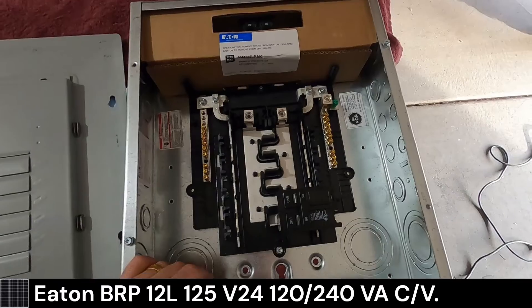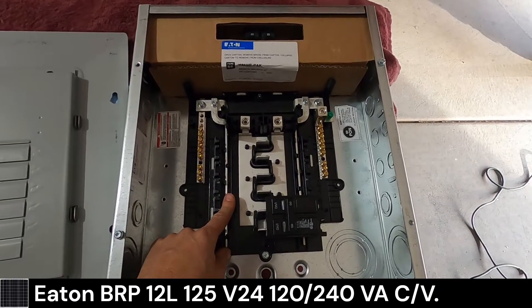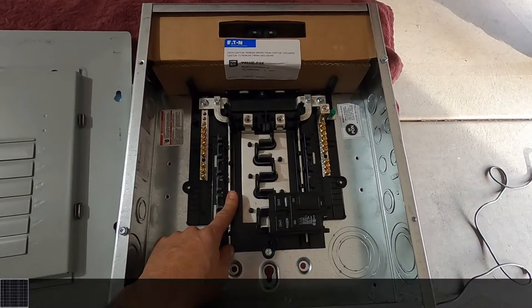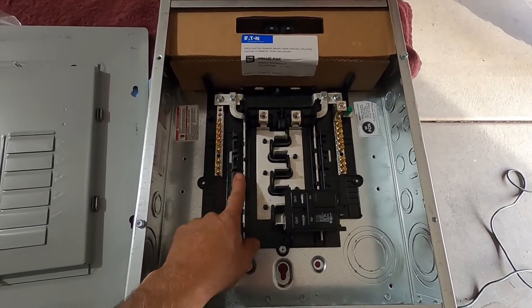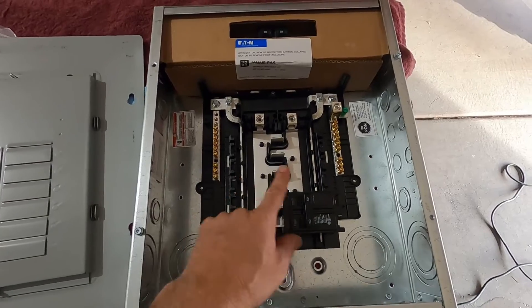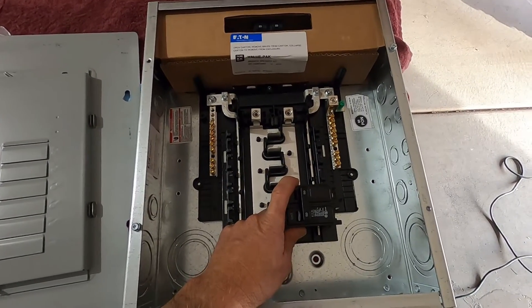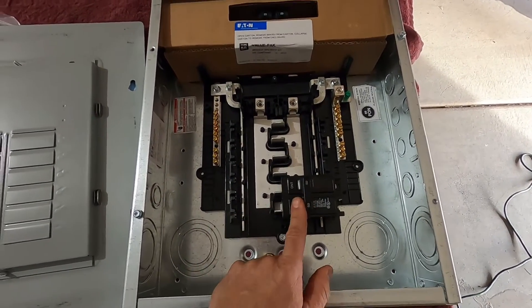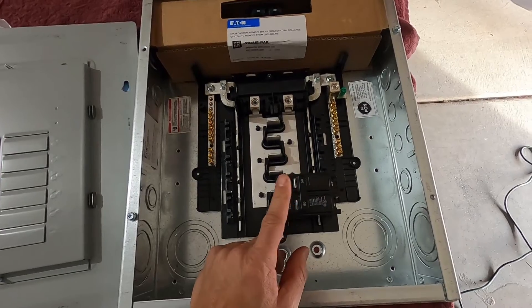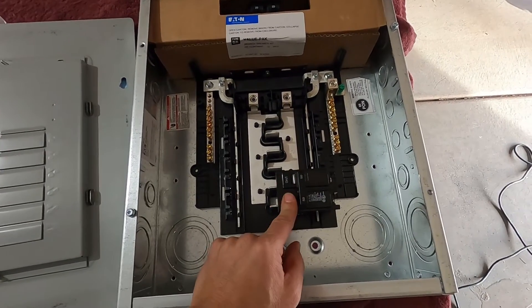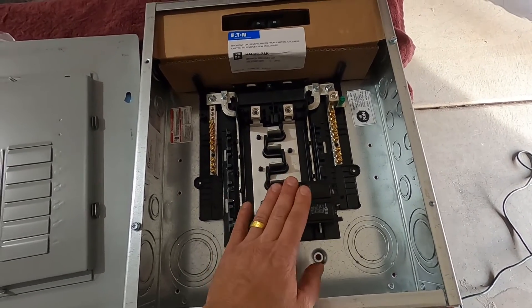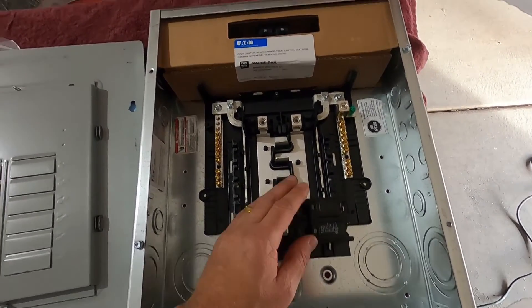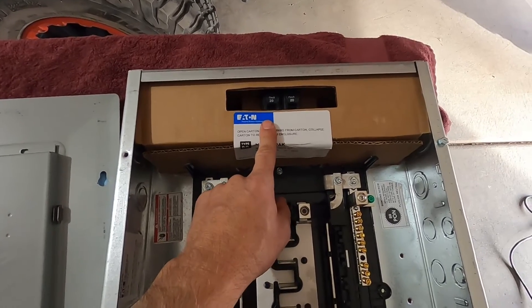Okay, what we have here is an Eaton 125 amp subpanel. This includes 12 slots. I can provide up to 24 circuits. I got this temporarily mounted here. I'm waiting on my 70 amp breaker. This will be the mains. And this comes with two 20 amp breakers.